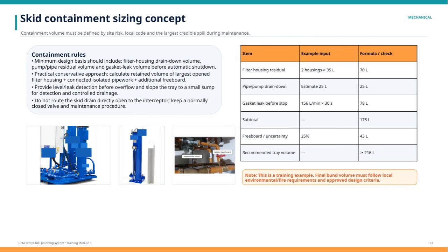Looking at the table, for example, 2 filter housings at 35 liters each contribute 70 liters. Pipe and pump drain down is estimated at 25 liters, and gasket leaks before shutdown at another 78 liters. This gives a subtotal of 173 liters, with an additional 25% freeboard to cover uncertainties, bringing us to a recommended tray volume of at least 216 liters. Finally, keep in mind that this is a training example. The final bund volume must comply with all local environmental and fire safety requirements, as well as approved design criteria.